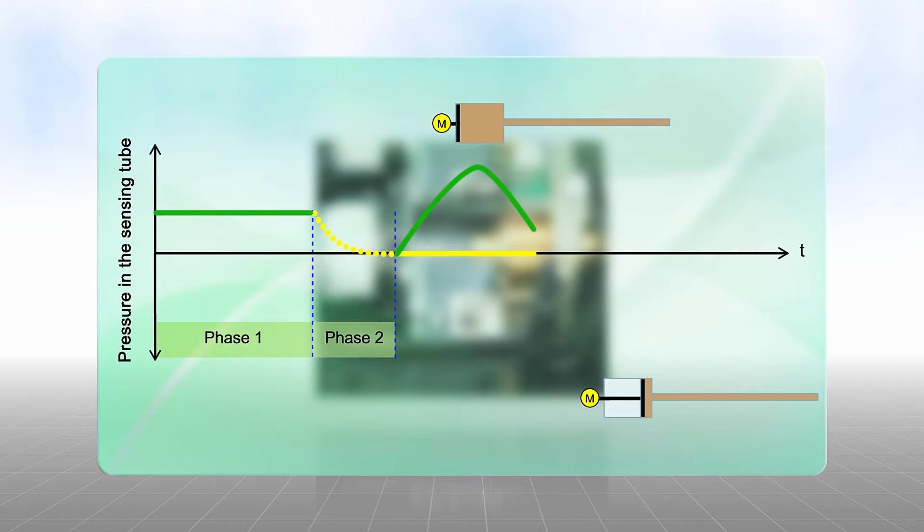The fully automatic sensing tube monitoring detects any errors, regardless of how improbable they might be. If there is a suspicion of a leak and at specific intervals, a monitoring device generates a defined overpressure in the sensing tube.